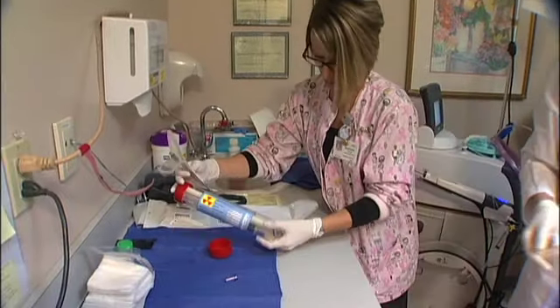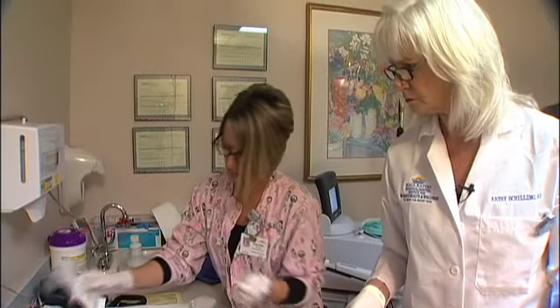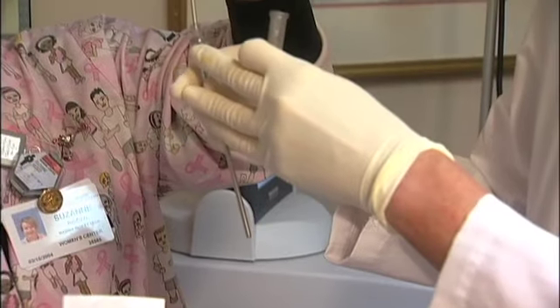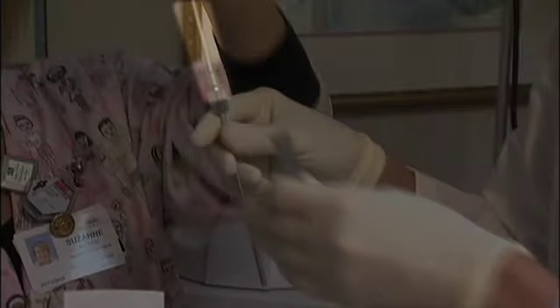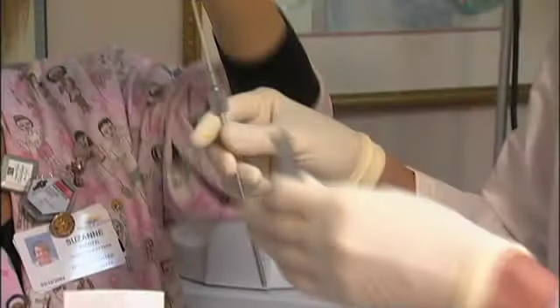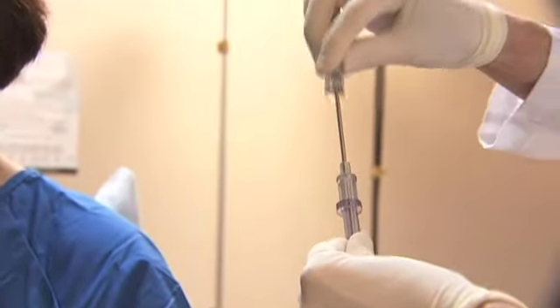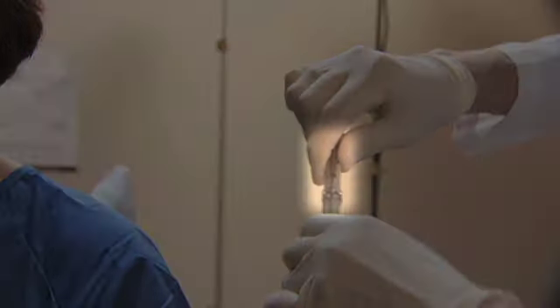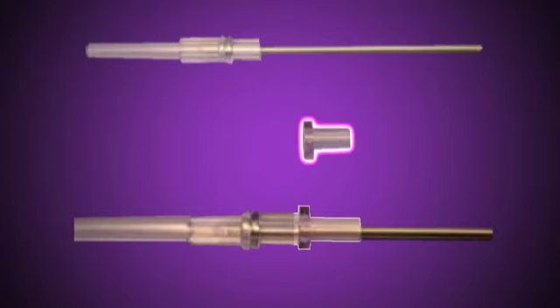With sterile gloved hands, remove the sterile line source casing from the package. A technologist then inserts the non-sterile radioactive germanium PET line source into the line source casing. Next, continuing to wear sterile gloves, attach the sterile casing handle to completely encapsulate the radioactive source. Place the Mammotome probe guide spacer piece onto the proximal end of the line source casing. If the probe guide spacer is not used, the line source casing will be too long and will not accurately locate the biopsy aperture with the lesion.